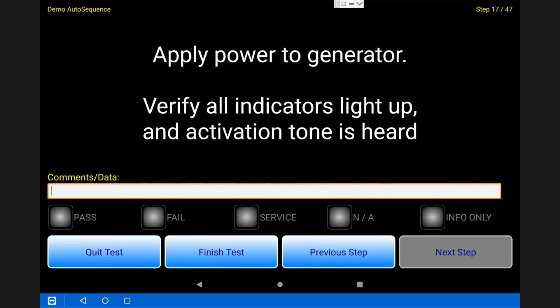So in this case, we're providing the ability to not only give detailed visual instructions via text format, but we also offer, and again, this is one of the efficiencies that we believe is so significant, the ability to add pictures. So in this case, for those that have never done an ESU PM, one of the key factors is to make sure that you have a test cable with the little pin on the test cable. So we feel that through a visual aid like this photo, you can more appropriately and quickly or efficiently give those instructions to your technician. In this case, we're using just a default sample device under test, or representation of the ESU unit itself. We will have a slide also showing one with an exact unit. So if you're building a specific one to a specific make and model, you can have those in there as well.